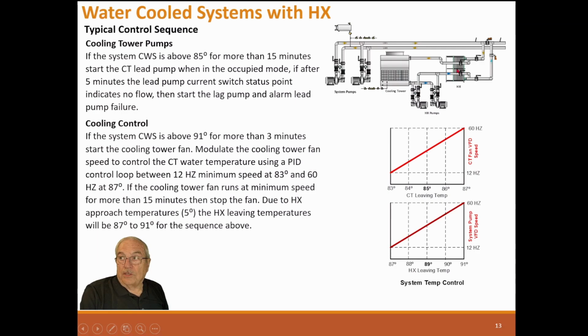So these are going to be 5 degrees, and normally that's a 2-degree heat exchanger and a 3-degree cooling tower, or something in between there. And instead of having 85 degrees here, you'll have 89 degrees here. So we're trying to maintain that temperature. Now these can all be lower as long as you have ambient loads that allow a colder temperature.